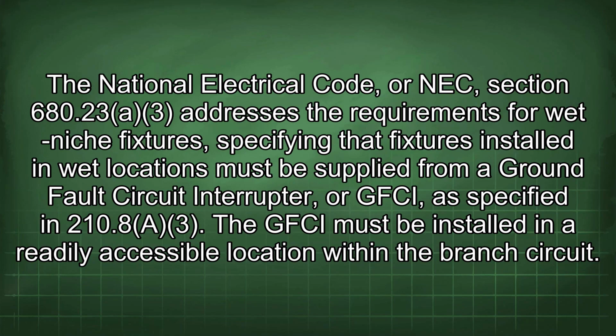The National Electrical Code, or NEC, section 680.23 addresses the requirements for wet niche fixtures, specifying that fixtures installed in wet locations must be supplied from a ground fault circuit interrupter, or GFCI, as specified in 210.8A3. The GFCI must be installed in a readily accessible location within the branch circuit.